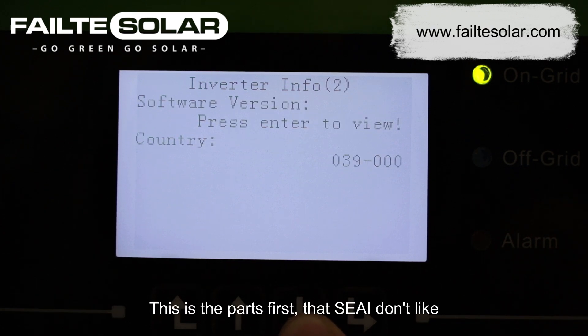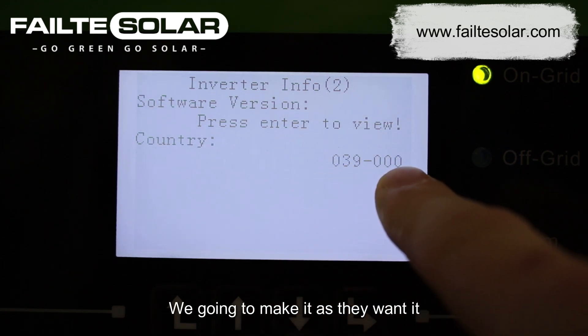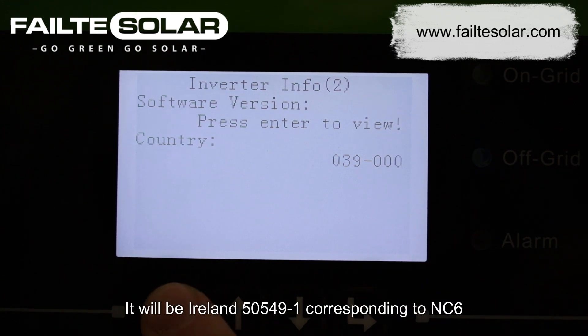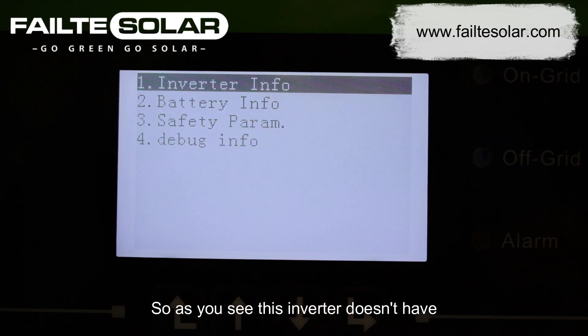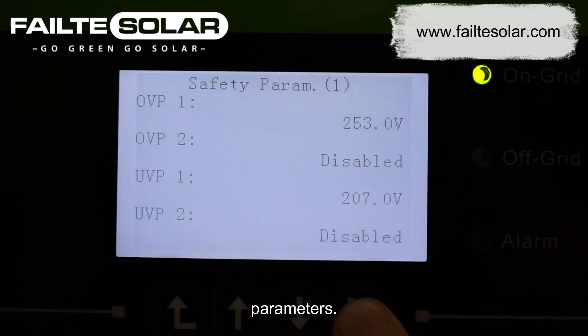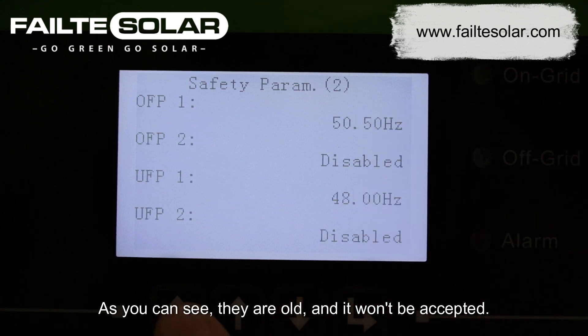This is the part that SEAI don't like because it's only showing 03900. We're going to make it as they want — it will be Ireland 50549-1 corresponding to NC6. As you can see, this inverter doesn't have the latest updates done. The second thing to check is the safety parameters. As you can see they are old and won't be accepted.